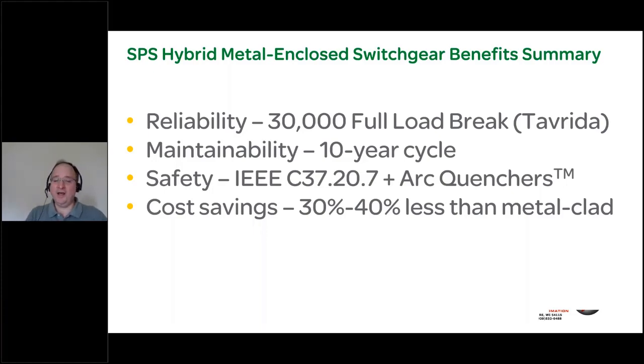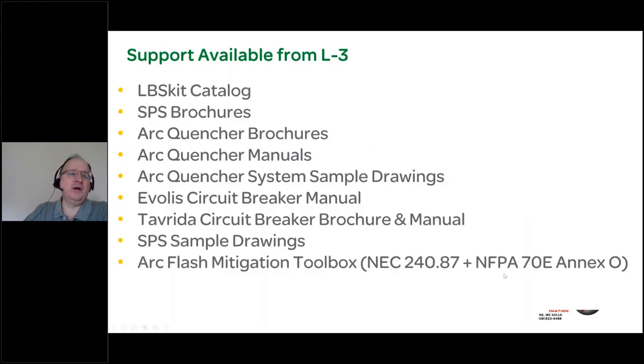And remember, anywhere that light sensor network is extended downstream, so you have motor control centers and substations and variable frequency drives, whatever you have that is fed from this equipment, those same arc resistant benefits can be extended to those assets. And of course, we cover that in detail in our separate arc quencher presentation. And cost savings: this varies by configuration, of course, but it's typically 30 to 40% less when you use hybrid switchgear as compared to traditional metal-clad switchgear.